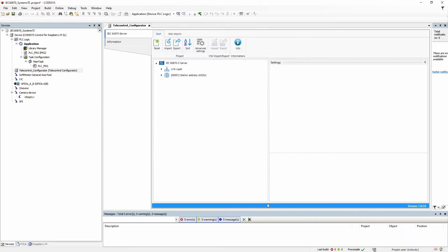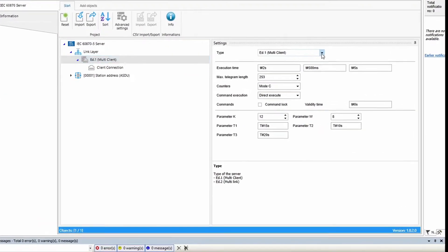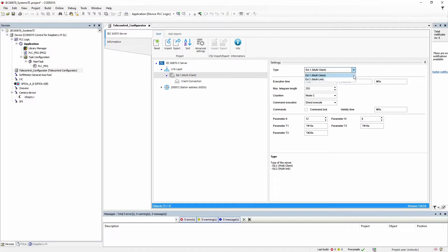By default, the project tree already contains the IEC 60870-5-104 server with the link layer. With multi-client selected, up to four client connections can be added, where each client connection uses an exclusive buffer memory, whereby each client receives the same information from the server and can send queries and commands to the server. With multi-link selected, several clients use the same buffer memory, where all these clients can be connected to the server on the link level, but only one of the connections is active for data exchange.